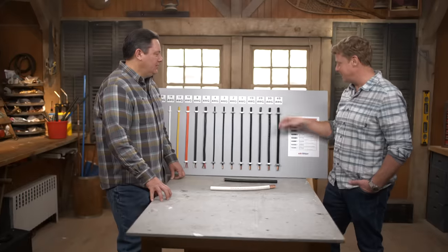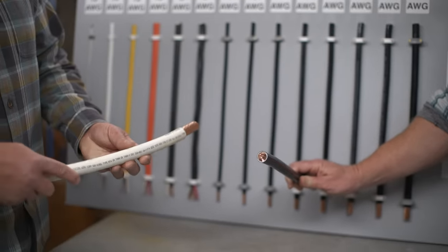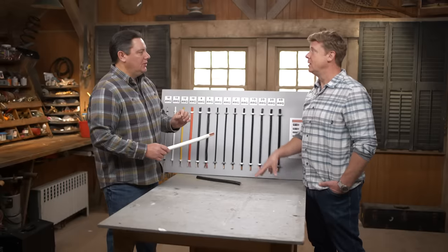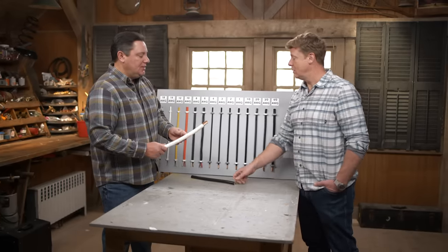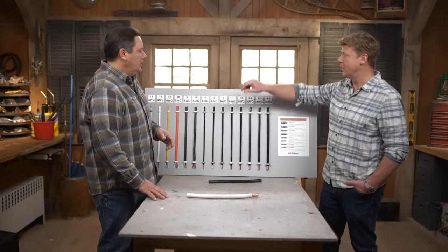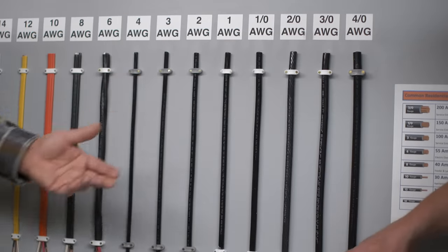So something much larger — this is 500 KC mil. If we really want to confuse the numbers: we go backwards till we hit 1-0, start going up, and then we go metric — kcmil, meaning 1,000 circular mils. This would actually carry 400 amps, which would be for a really large residential service, more of a commercial or industrial application. For a 200 amp service in a home, if we're doing copper versus aluminum, we're going to use 3-ought.